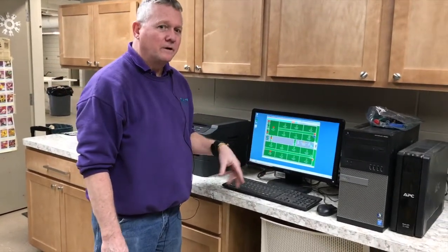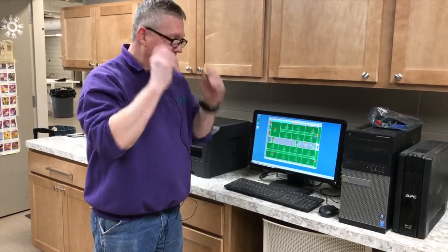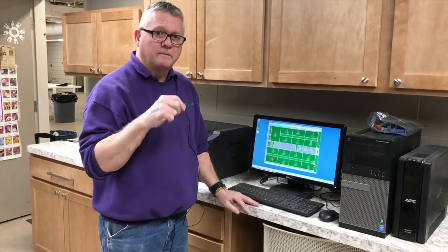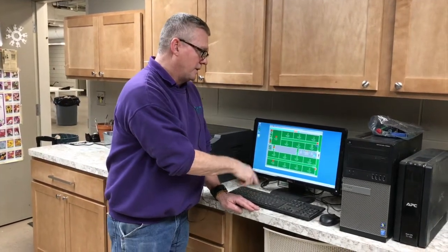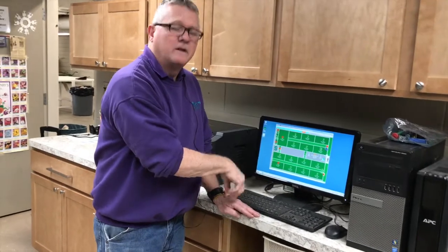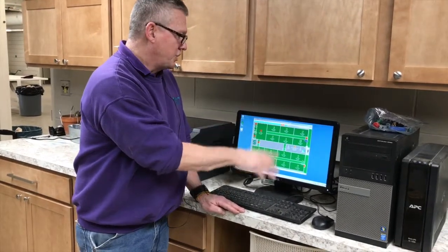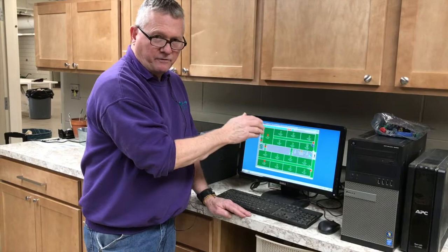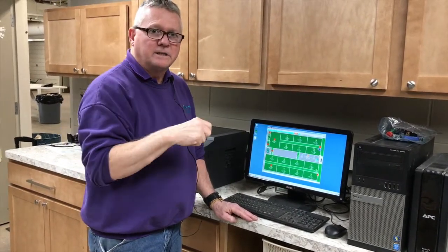And we're going to start right here with the brains of our environmental controls, this computer console here. What happens is out in the greenhouses there is a temperature sensor in each of the houses and two in each hallway. And they will take readings every 90 seconds, and then that information goes to the panels in the hallway, and then from there goes to the computer. The computer reads that data, analyzes it, adjusts the different devices, say the vents or fans, and then sends that information back to the greenhouses, all within 90 seconds.